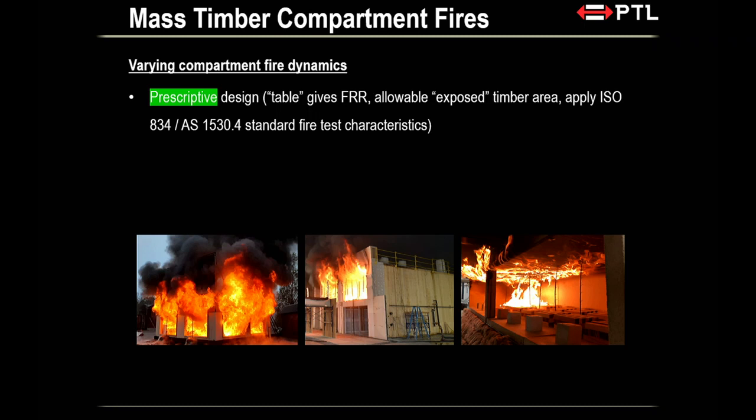Some people might challenge and say, look, I've seen an experiment, it's going at 1 mil per minute. Fire engineer doesn't care. Just use 0.65. I'm on a prescriptive design, don't bother me about it. Right? No, we have to communicate. I will explain to you why shortly. But prescriptive design: read the table, use the standard value, and off you go.